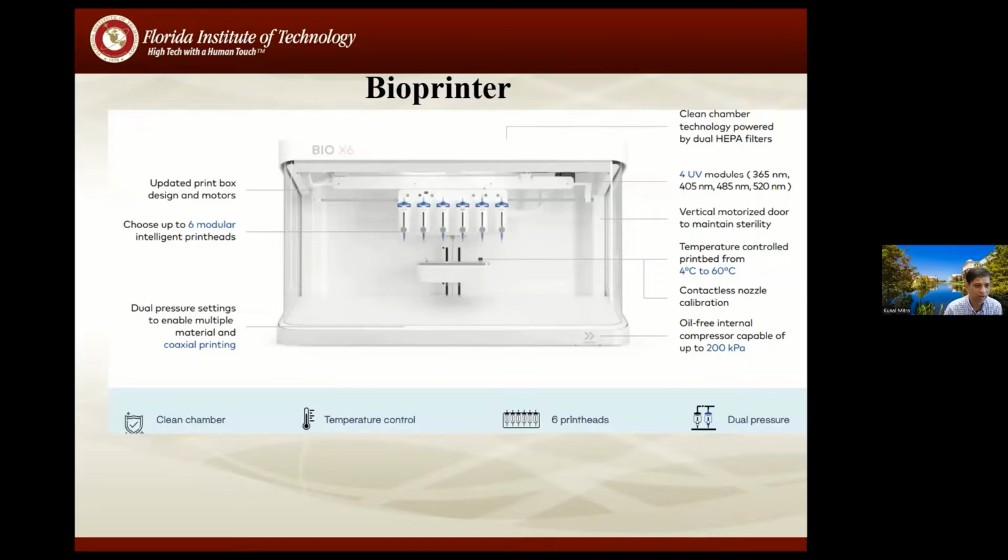So if you're familiar with the bioprinter, you may have seen this is an extrusion bioprinter. It has got 6 heads. As I said, we are not using 6 heads, but ideally you can use 6 types of materials and 6 types of cells. Complex, we are using 3 at most. So, as I said, there's room. It's not just a regular printer where you press a button and you get a tissue print. A lot of optimization, pressure. Just yesterday, in fact, we were doing some experiments in the lab. We are doing one type of new biomaterial, and as soon as we mix it with cells, the extrusion parameters change compared to without adding the cells. So it is that level of complexity.